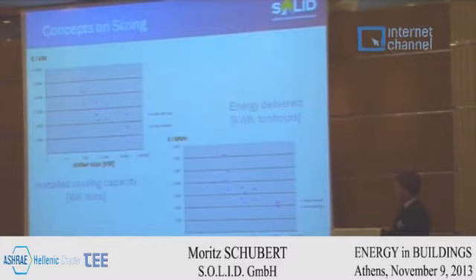I can show this quite nicely with chiller size. When you have a chiller around 100 kilowatt cooling power, the investment cost for the absorption chiller in Europe per kilowatt is around 3,000 or 4,000 euros. But beyond 100, on a logarithmic scale, starting from 300, 500 kilowatt cooling power, the specific cost goes down a lot. So for a system of 1,000 kilowatt, the specific cost is only around 2,000 or even lower.